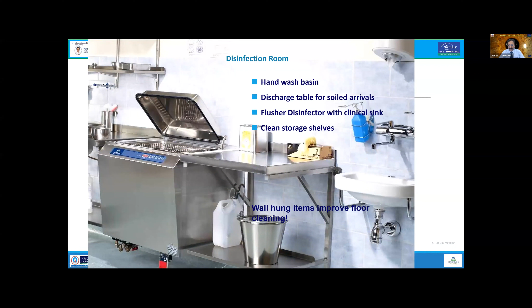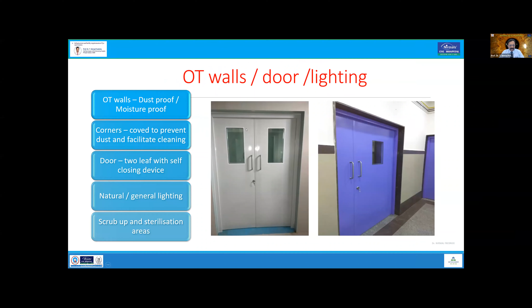The OT walls, ideally, should be dust-proof and moisture-proof. The corners have to be coved, and doors ideally should be 2-leaf with self-closing device. Natural lighting in ophthalmic setups, natural or general lighting is essential. You also need to plan the scrub up and sterilization areas.